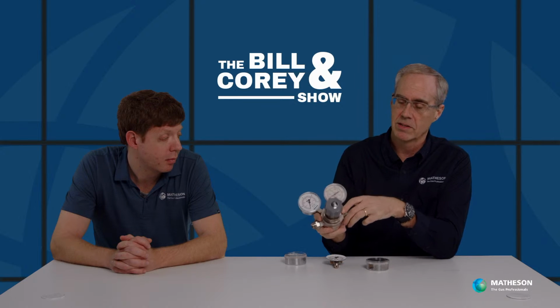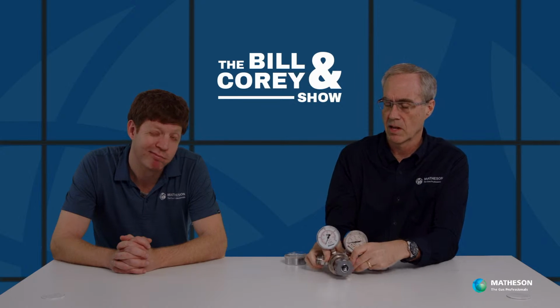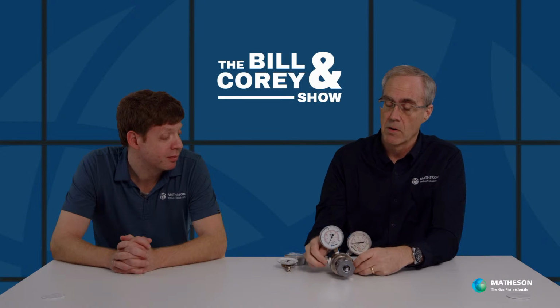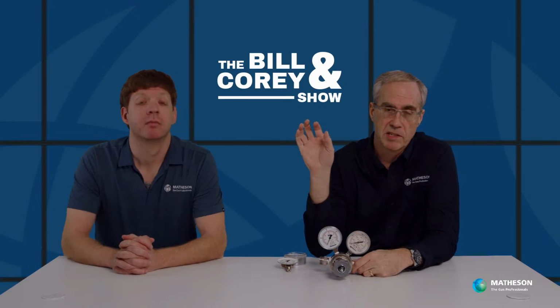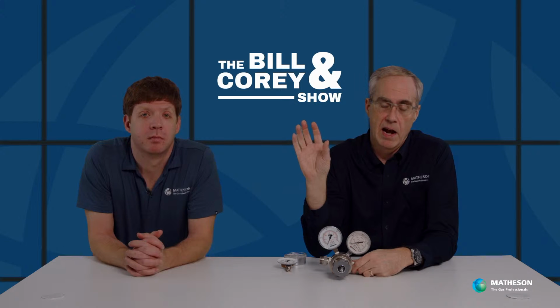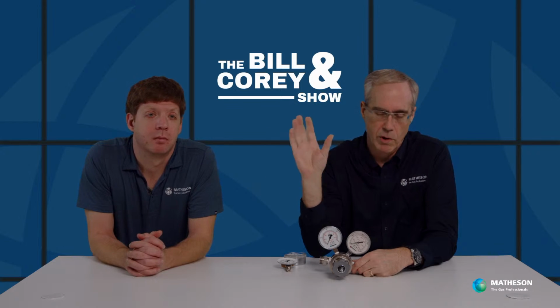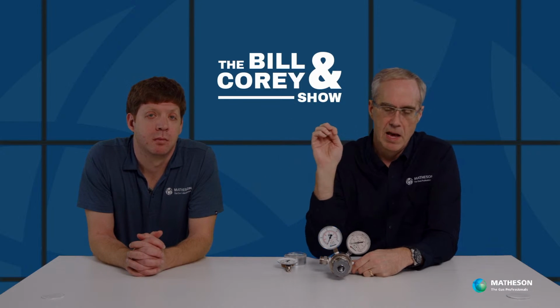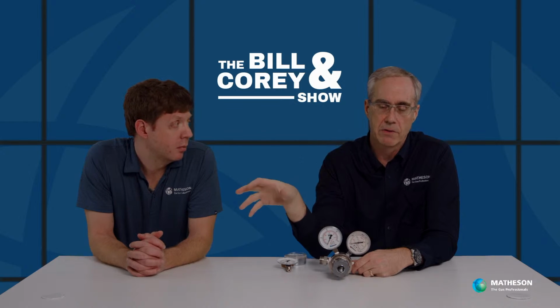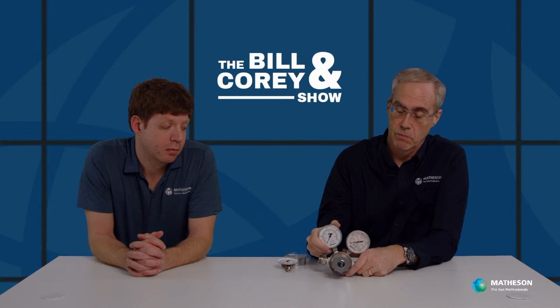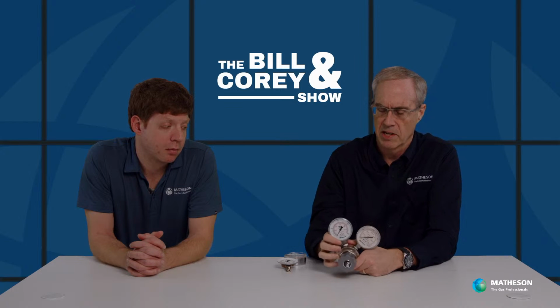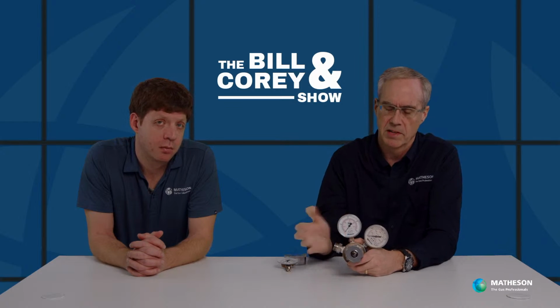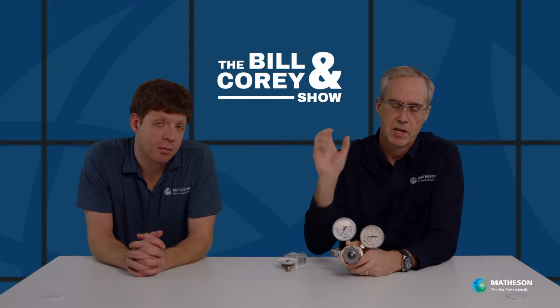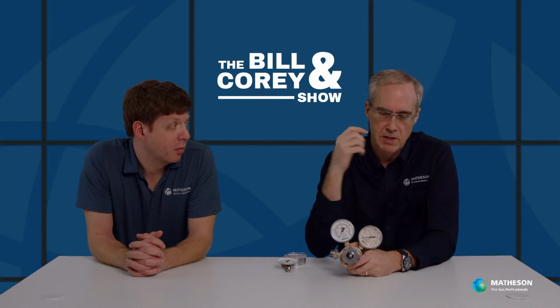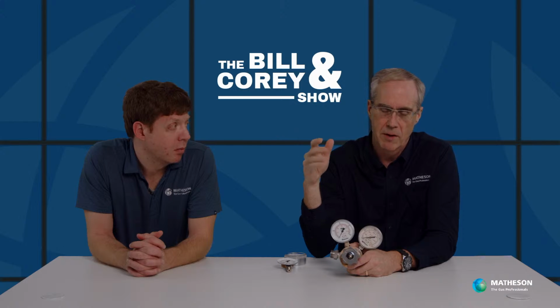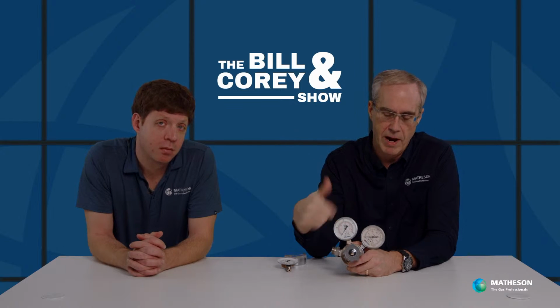On a new installation is probably where you're going to see these kinds of things. It could have been someone pressurizing downstream at a higher pressure for leak testing, or setting something up, and they might have overpressurized downstream. I think they had a 100 psi delivery, 200 psi gauge. So if they were pressurizing downstream and it got to 300 psi, you would have wrapped it around.